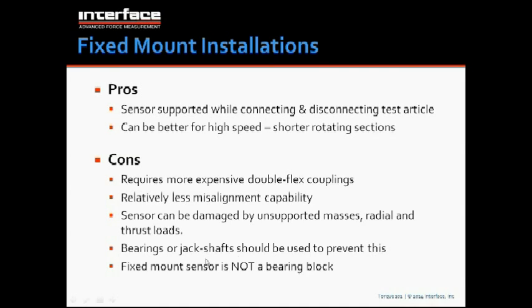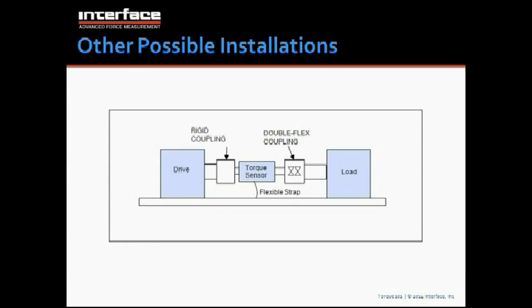In case there may be radial loads, another bearing should be used. The sensor is never to be designed into the system to be used as a bearing block. It will be destroyed. Other possible installations: this is acceptable but not necessarily desirable. You have a rigid mount, a floating sensor, and then a double flex on the other side.